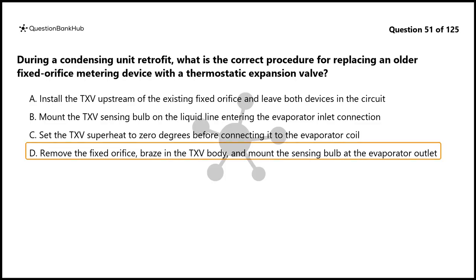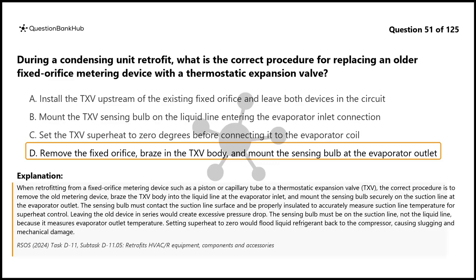The correct answer is D. When retrofitting from a fixed orifice metering device such as a piston or capillary tube to a thermostatic expansion valve, or TXV, the correct procedure is to remove the old metering device, braze the TXV body into the liquid line at the evaporator inlet, and mount the sensing bulb securely on the suction line at the evaporator outlet.